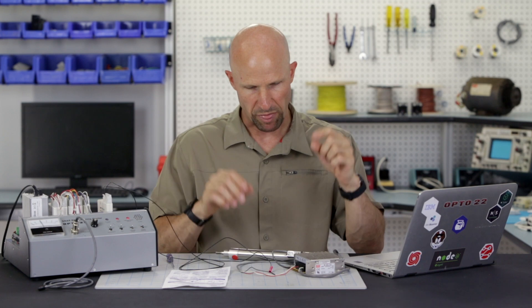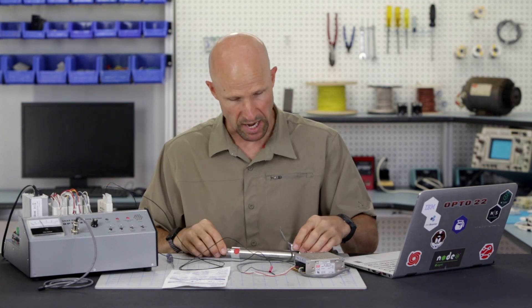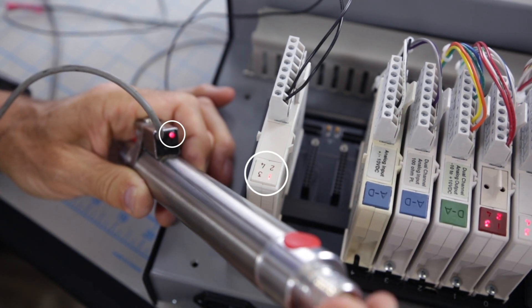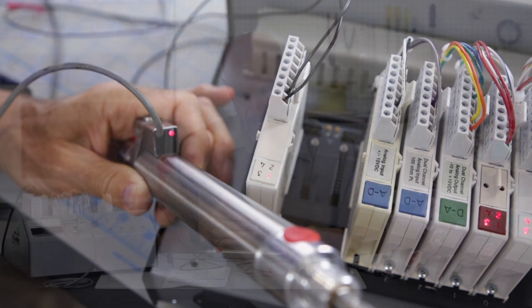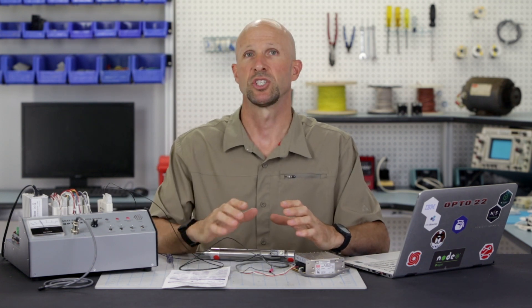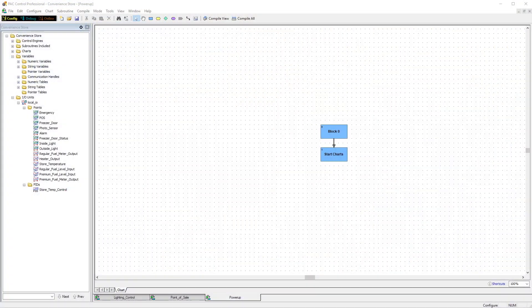Next, we snap the module into position 7 at the end of the rack. Now let's make sure that both the proximity sensor LED and the module LED are both working as expected. Every time the shaft gets to the end of the cylinder, both the proximity sensor and the module LED work as expected. So that's the wiring and the module installation done. Let's move on to the laptop and configure the sensor in the software.